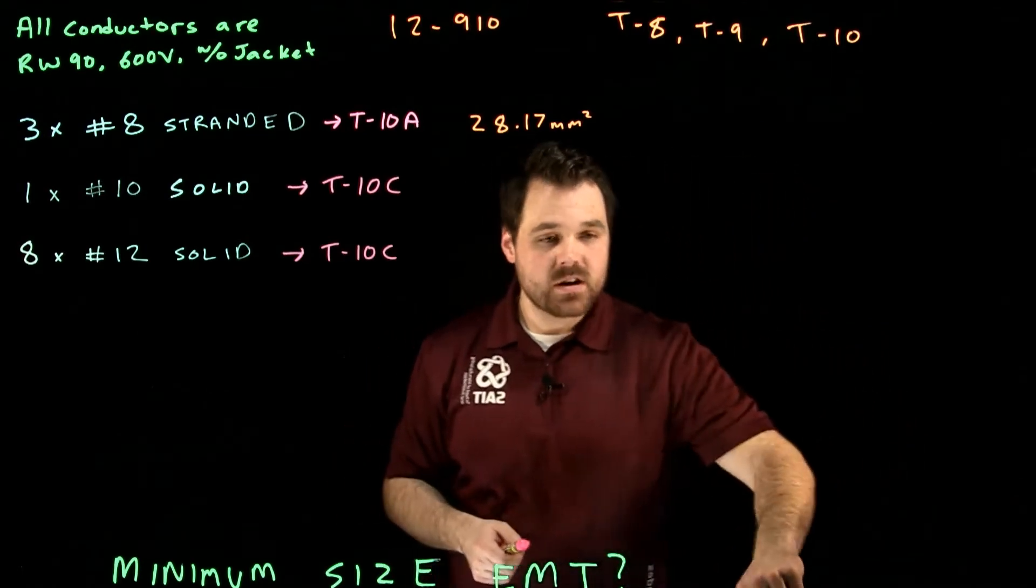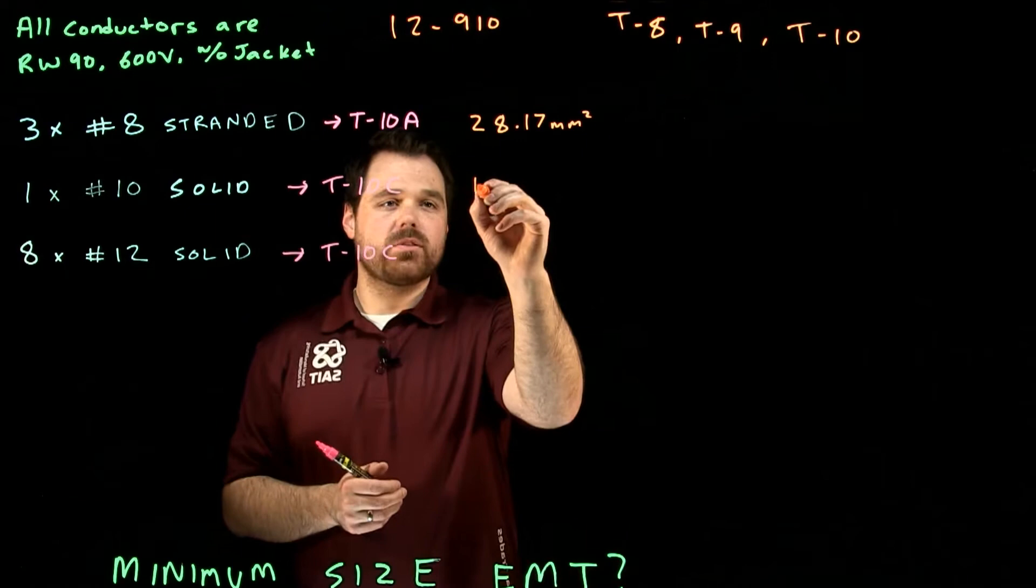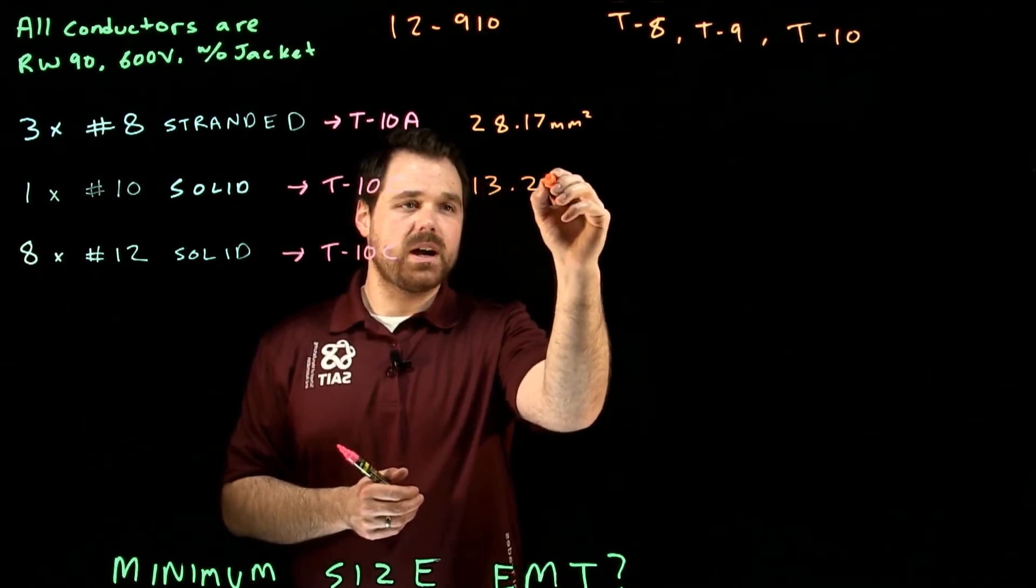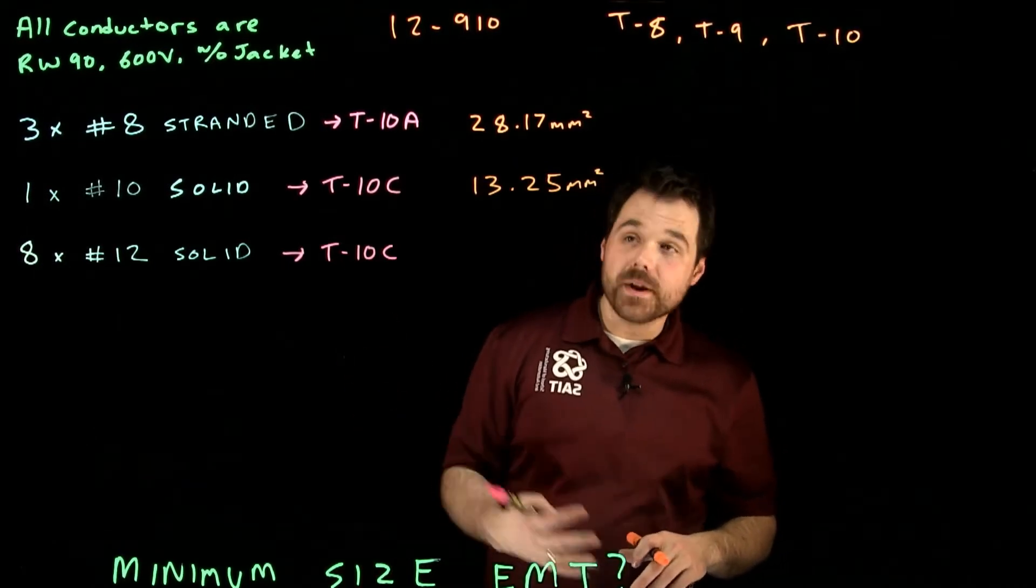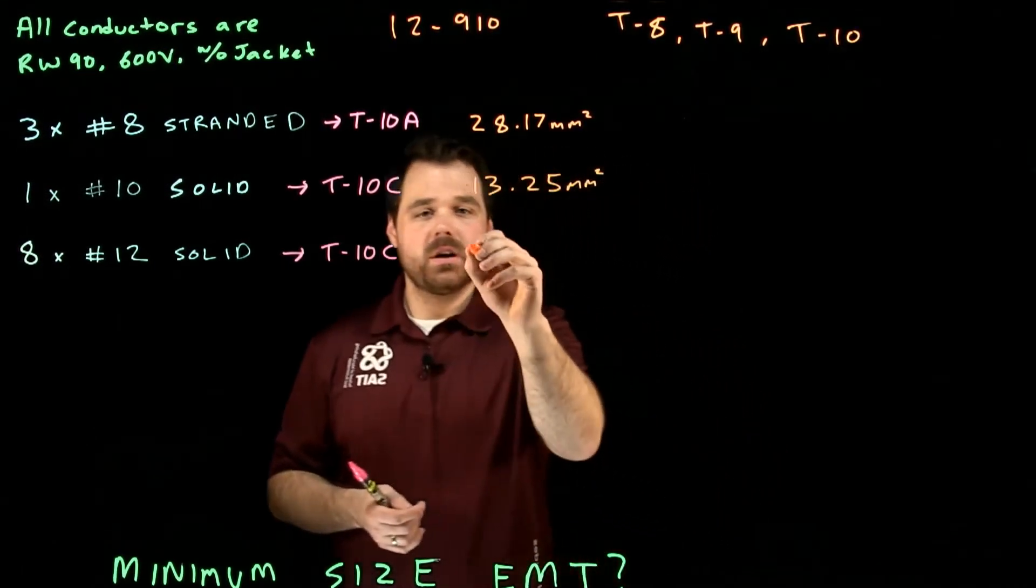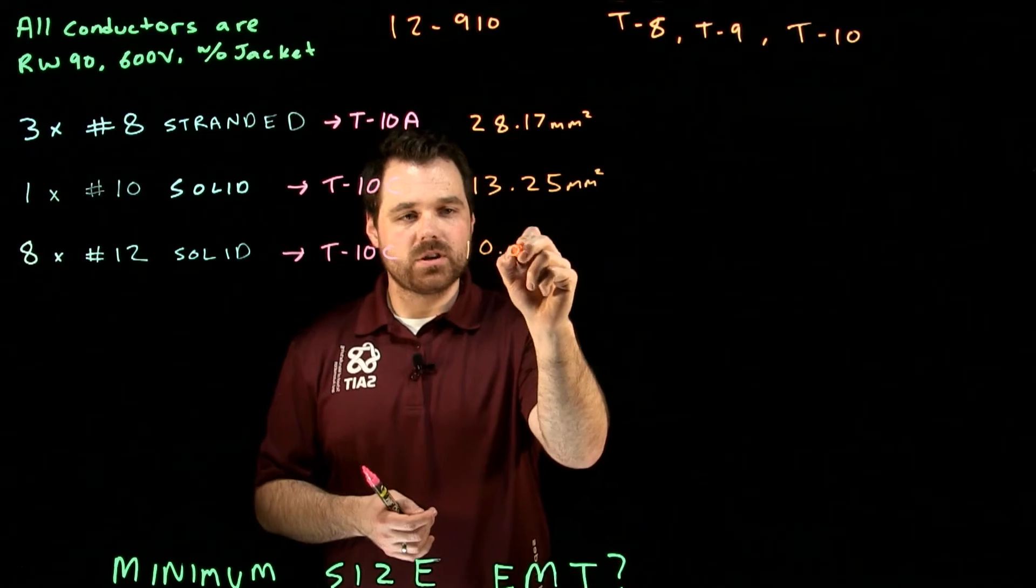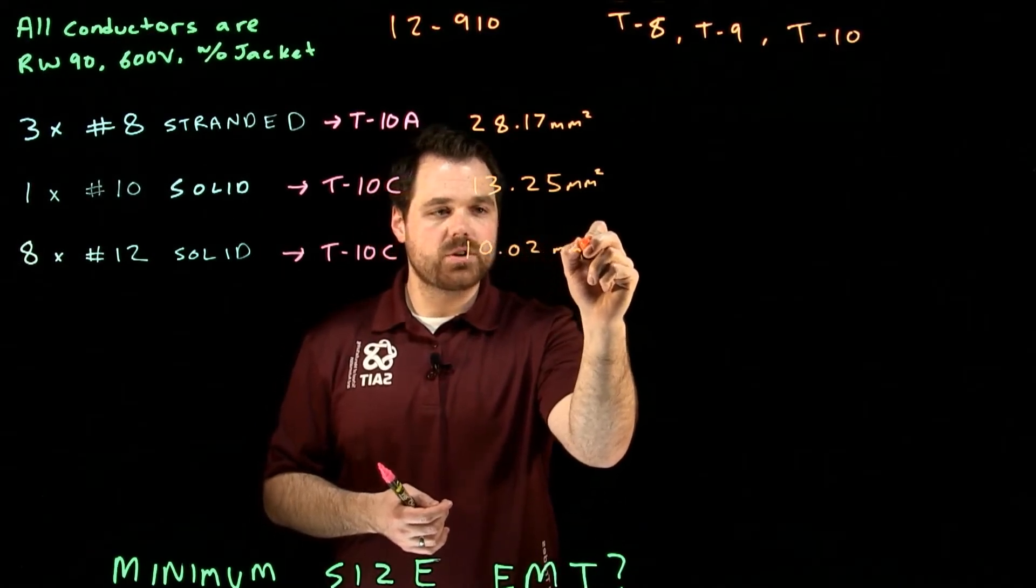So one number 10, we find out is good for 13.25 millimeters squared. That's how much space it takes up in the conduit. One number 12, this is just for one, takes up 10.02 millimeters squared.